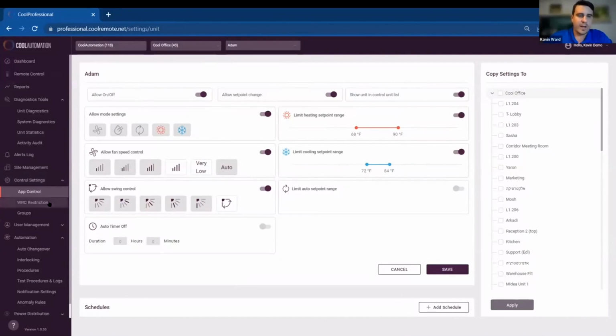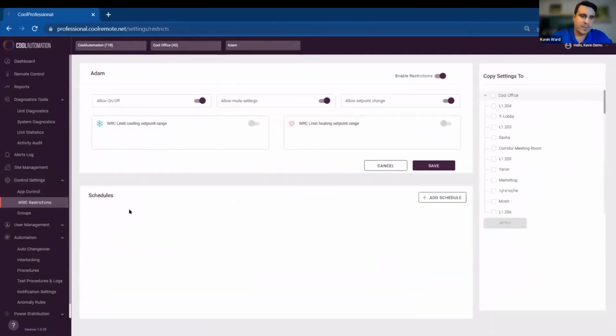And locally from the actual wired controllers, we can apply the same limitations. So we can activate a cooling and heating set point range, move this to the appropriate temperatures, and apply that to specific controllers. They may feel like they're able to set the change from the controller, but the cloud-based logic simply reverts that back so that the set point is always within your specified range. And this will allow you to make sure your system isn't overcooling or overheating. You're always within a preferred range that optimizes the efficiency of your building.